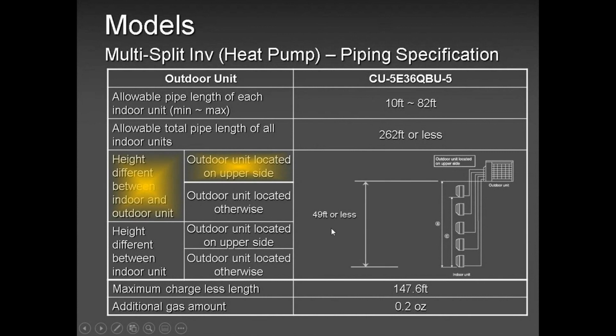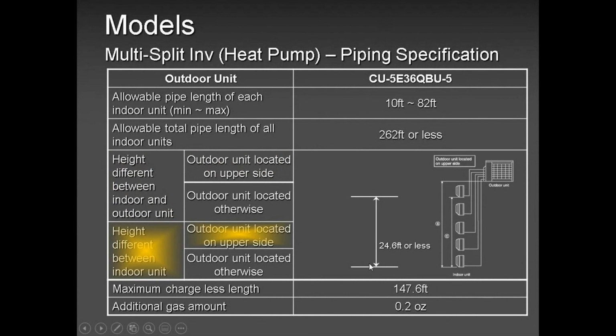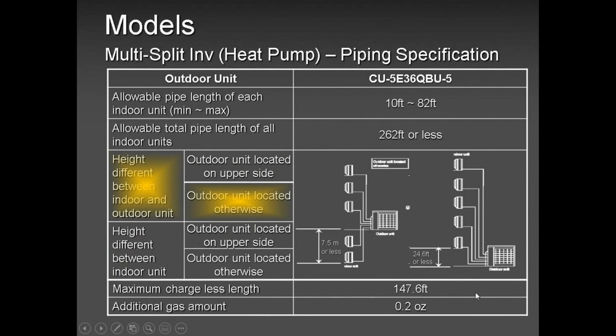On a single zone, in most models, it is charged for 24.6 feet. Above 24.6 feet, you need to add. In this 5 zone, the system is charged for 147.6 feet, which means if you cross this pipe length, you need to add refrigerant. In this model, a total of 262 feet is maximum, 82 feet per indoor unit. So you have enough pipe there to play around. I don't think you will ever cross 262 feet. Okay, so please keep that in mind. 262 feet is maximum. The unit is charged for 147. After 147, you will have to add 0.2 ounces.